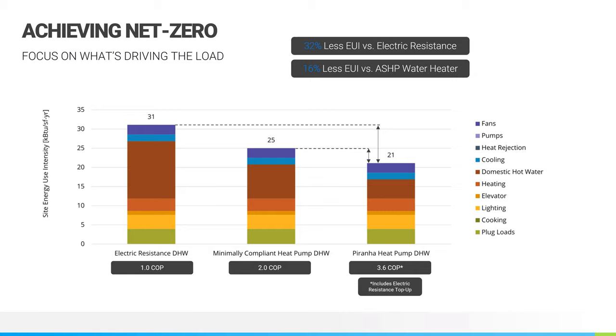So that was a big driver there, because this allowed them to truly achieve that net zero, because they had so much less energy that they had to make up on the consumption side with solar panels on the roof. So this is really where a lot of developers will get caught up and say, well, net zero is not cost effective. And it's like, well, if you're using traditional air conditioning, heating, and those types of technologies, I would agree with you. It can get very cost ineffective, because the amount of solar that you're going to need to overcome that large energy use intensity on that site.